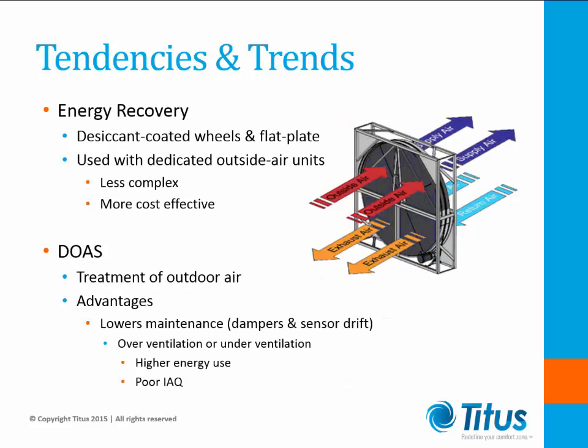Let's take a minute and look at a couple other configurations or build designs within the air handling unit. For instance, the energy recovery. There are 2 types of wheels, an enthalpy and sensible wheel configuration. Enthalpy is the total energy transfer, which is the humidity and temperature of the airstream, whereas sensible is only the heat that is transferred. The humidity is unchanged.